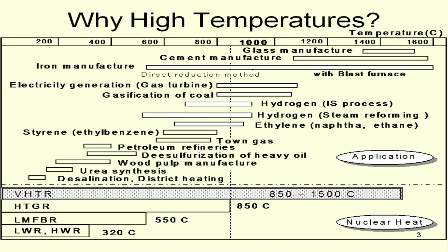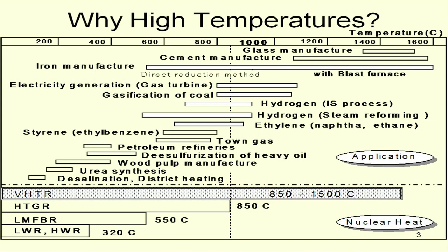A second aspect of why we want high temperatures is process heat applications. If you look down at the bottom here, you see rough ranges of temperature capabilities of various reactors. This is sort of existing generation HTGRs, and then the VHTR, which is sort of Gen 3 plus to Gen 4. And up above is the temperature requirements for various industries.